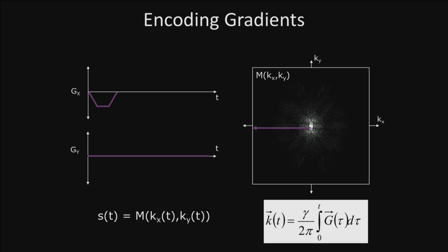So what K-space says here is that where we are in K-space, or where we're basically acquiring data, is the net effect of our gradients. The frequency encoding gradient here is doing something like this in K-space, and we refer to this as the K-space trajectory, the path by which we are sampling data or crossing K-space here.